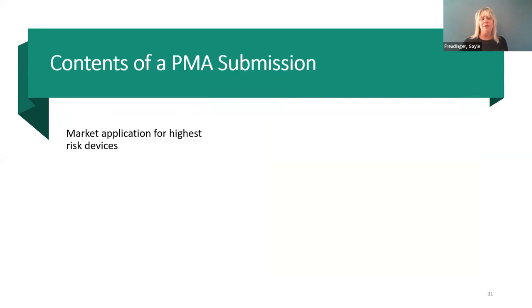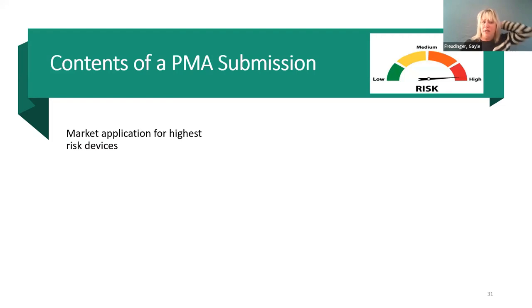Okay, talking about the PMA submission. The PMA, again, is the pre-market application. It's for the class three devices, and it's more in depth than a 510K. It's used to prove that your device is safe and effective, but it typically requires clinical trials on human patients and participants, along with laboratory testing. And the standards are much higher. So because it's the highest risk, the FDA requires about 180 days to accept or reject this application.